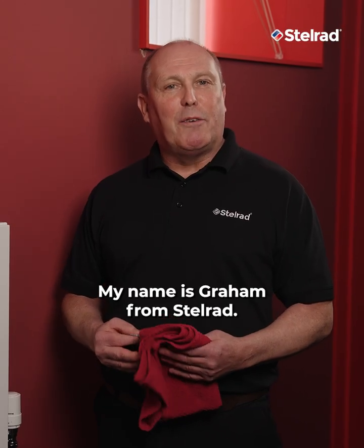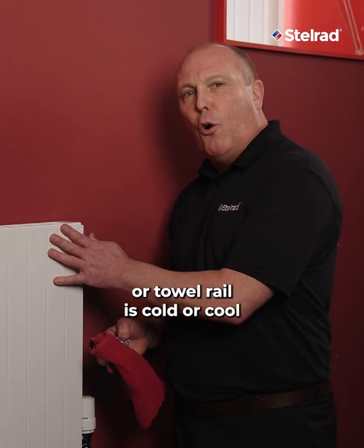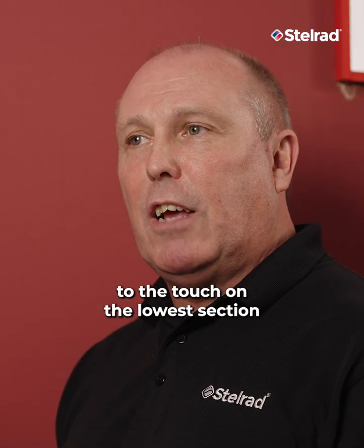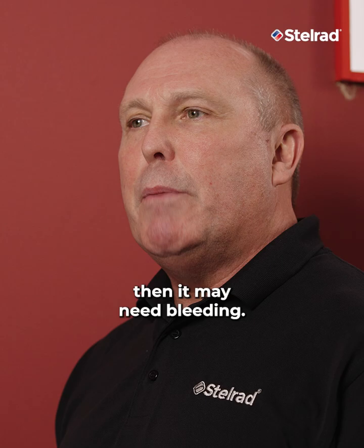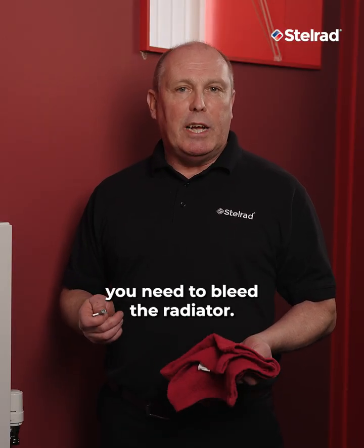Hello, my name is Graham from Stelrad. If the top section of your radiator or towel rail is cold or cooler to touch than the lower section when the heater is turned on, then it may need bleeding. To release the trapped air, you need to bleed the radiator.